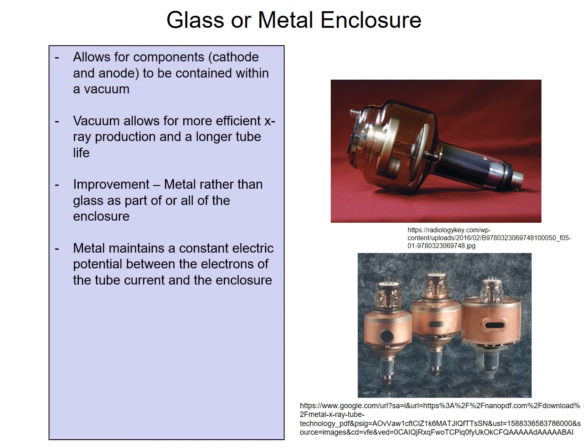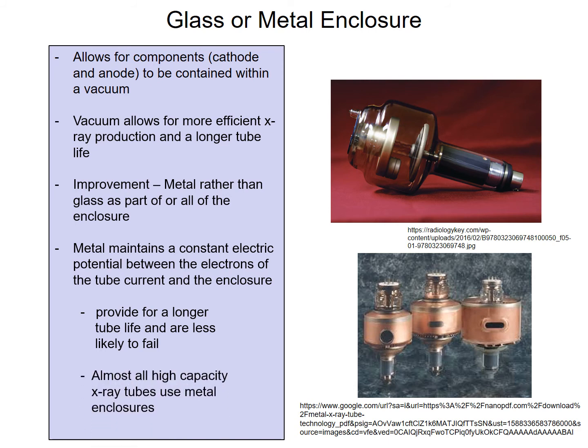Why is metal being used? It maintains a constant electric potential between the electrons of the tube current. Remember, that's the electrons streaming across and the enclosure itself. You get basically then less arcing occurring. So these metal tubes provide for a longer tube life. They're less likely to fail. And almost all high-capacity X-ray tubes today use metal enclosures.